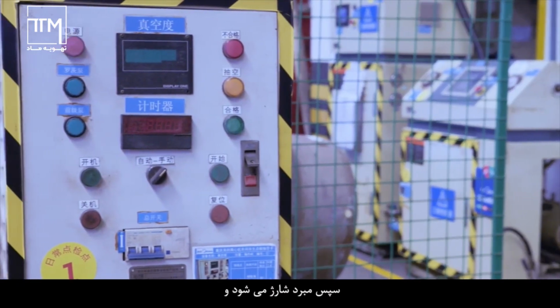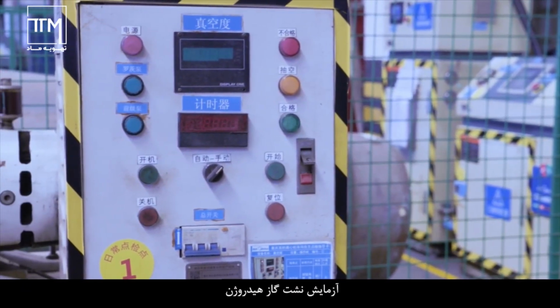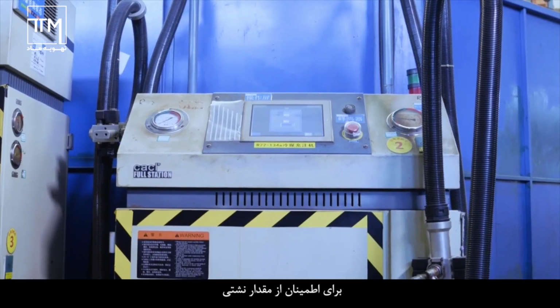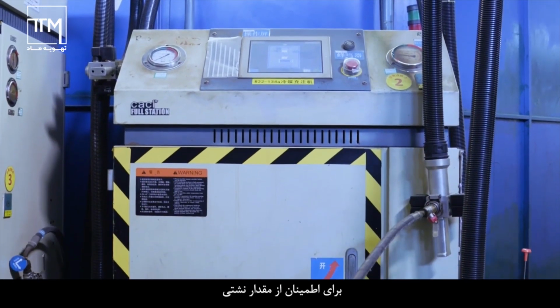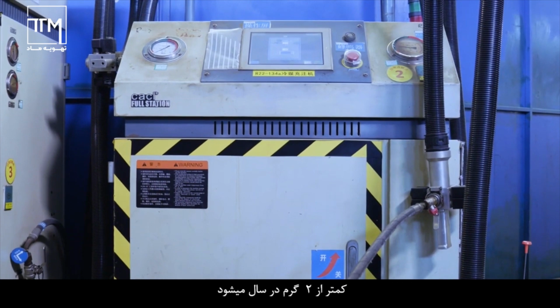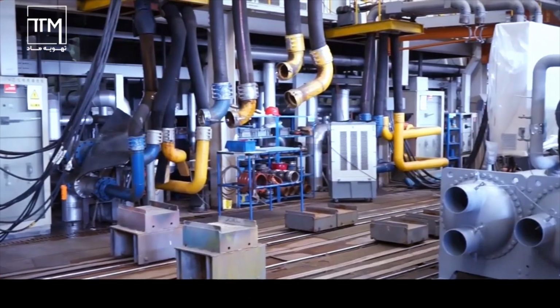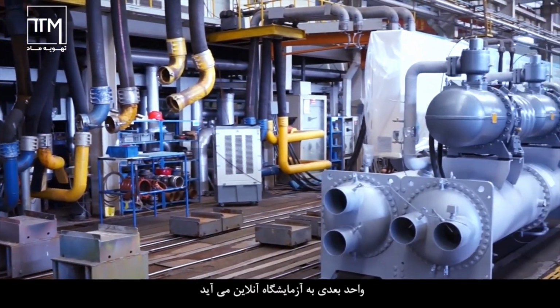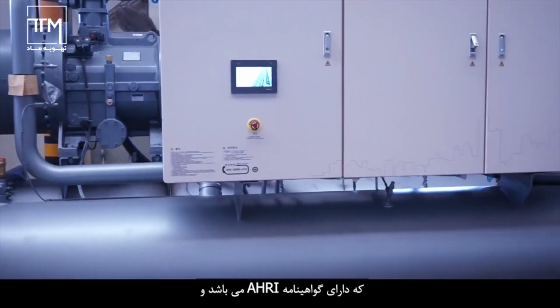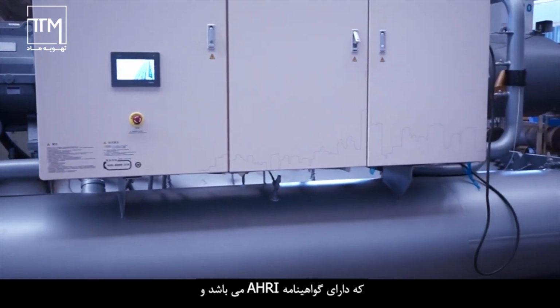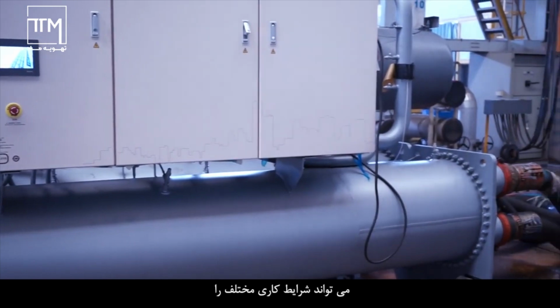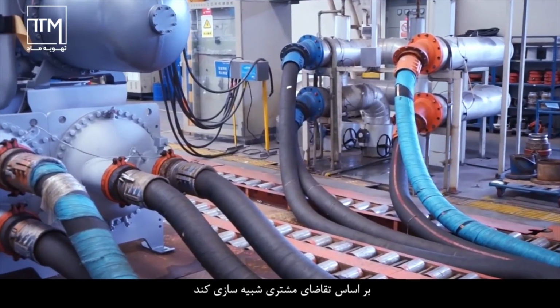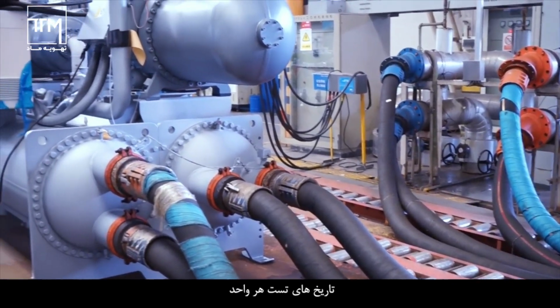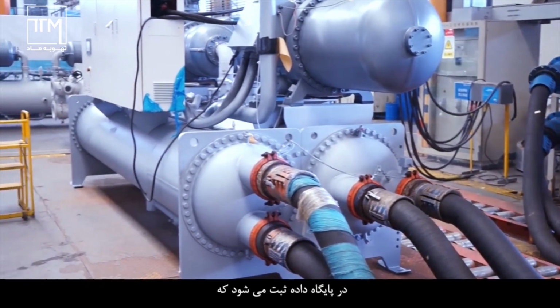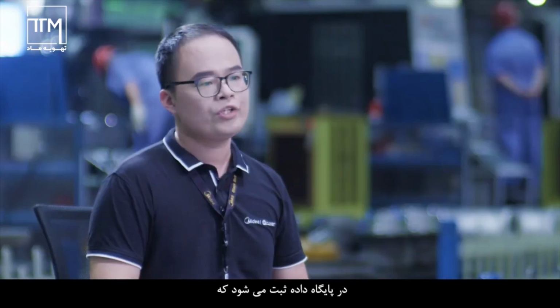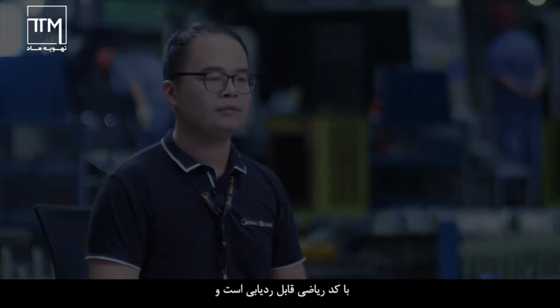Then the refrigerant will be charged and the halogen gas leak test will be carried out to ensure the leakage value is less than 2 grams per year. Next, the unit comes to the online lab, which is AHRI certified. It can simulate different working conditions based on client demands. Testing data of each unit will be recorded into a database, which can be traced by mass code.